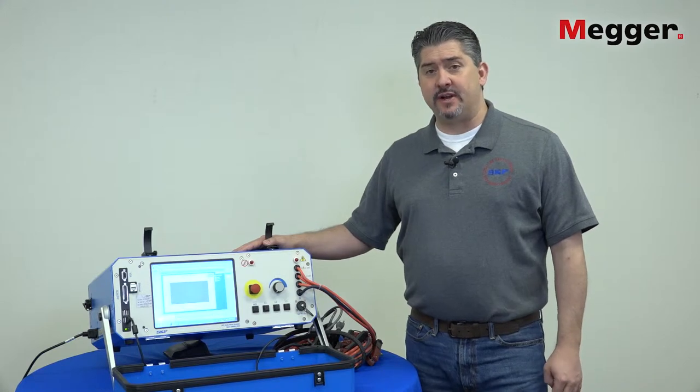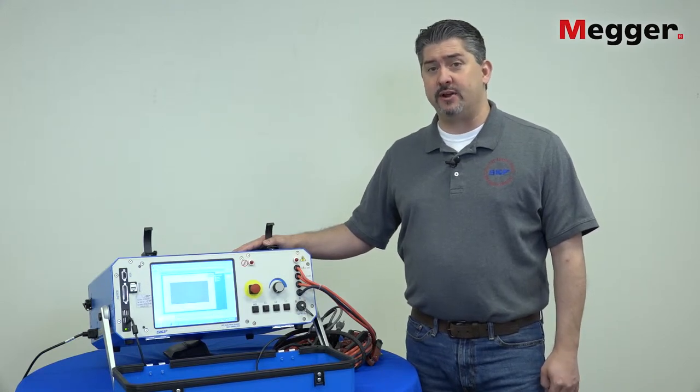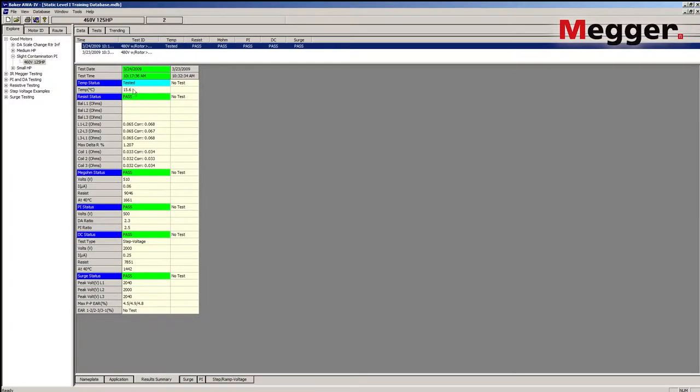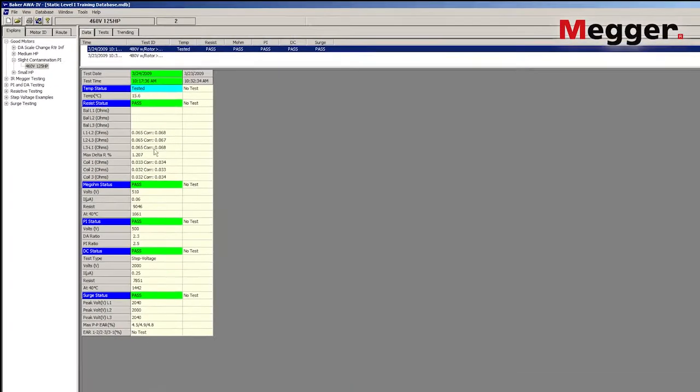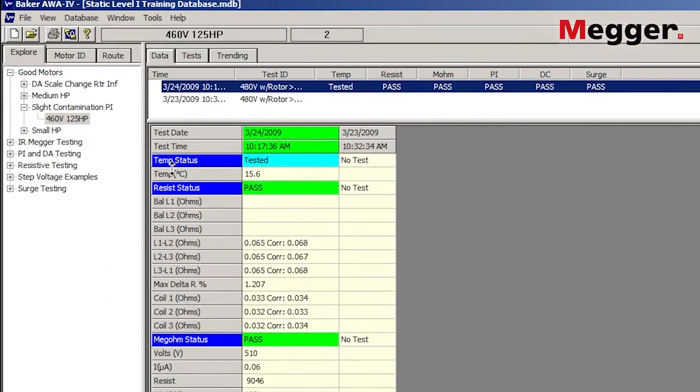In this video, we'll be covering data analysis and reporting with your Baker AWA. So let's go through the parameters. We have the temperature at which the stator was at the time of test that was entered. Even if you enter in degrees Fahrenheit, the value is saved as a degrees Celsius measurement.